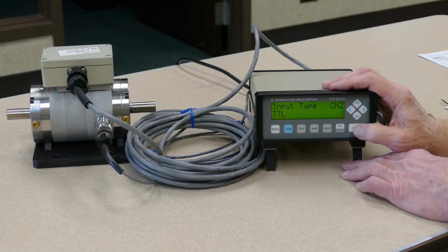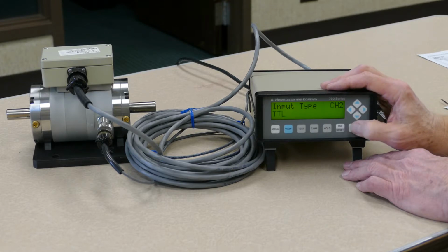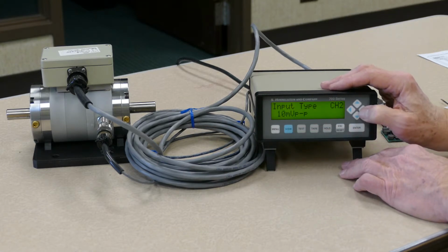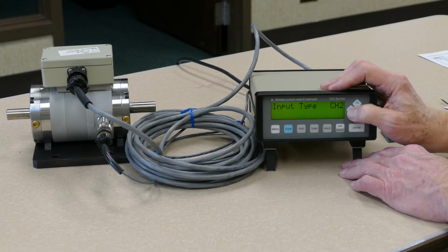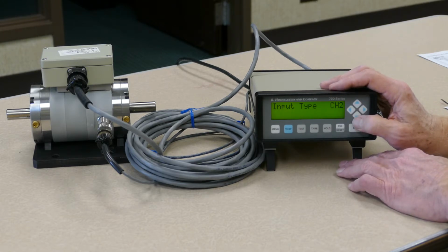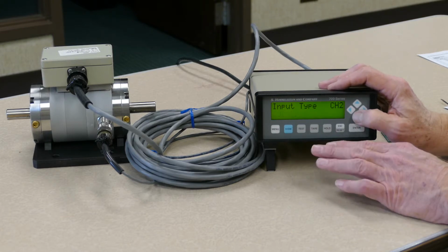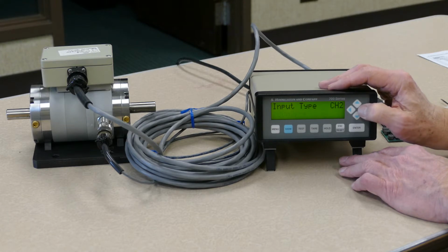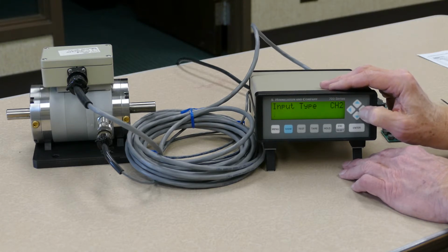Now it's asking for the type of input. There are a number of different pickups that we can connect to, either a 2-pin passive pickup or a 3-pin zero velocity pickup. By hitting the enter key, we can scroll through the available input types, starting with a 10 millivolt peak-to-peak input type, which would be from a passive pickup. Any of the millivolt inputs will be from a 2-pin passive pickup, and we allow you to select from 10 to 200 millivolts peak-to-peak, depending upon the amount of electrical noise that may exist in your installation. In this particular case, we're connecting to a 3-pin zero velocity pickup, and that would be the TTL input.